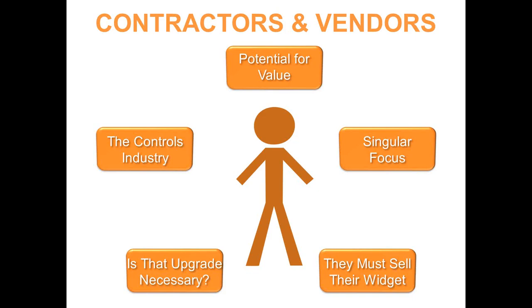There have been a number of studies done by Energy Star that show that most buildings with VAV and high efficiency chilled water systems actually operate no better than those buildings that do not contain those types of high efficiency systems. And this is primarily a cause of how the control system interacts with those particular pieces of equipment in a building. So the basis of creating efficiency in existing buildings is essentially how that control system operates. You can have the most efficient equipment in your building, but if you're not controlling it correctly.